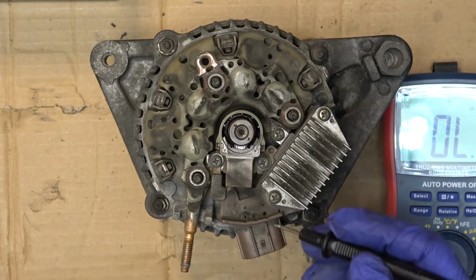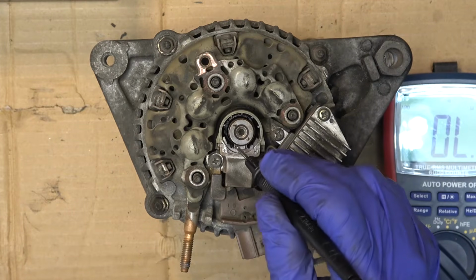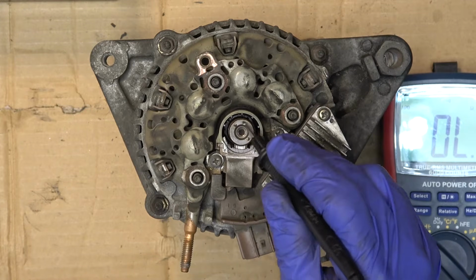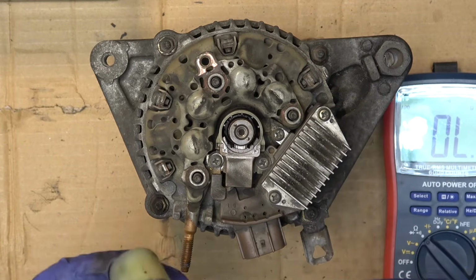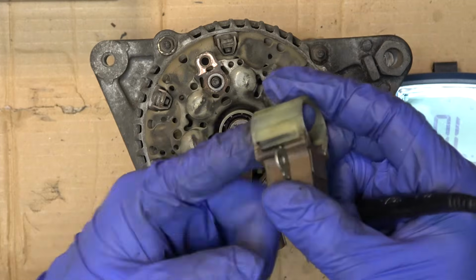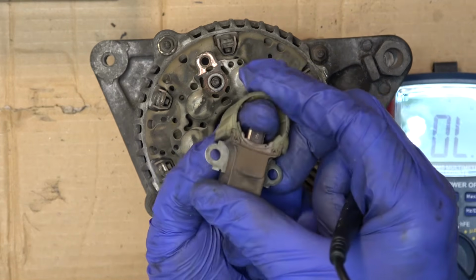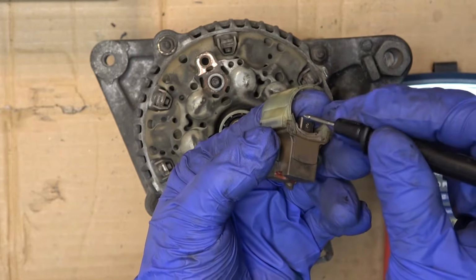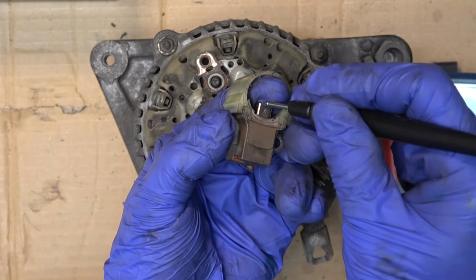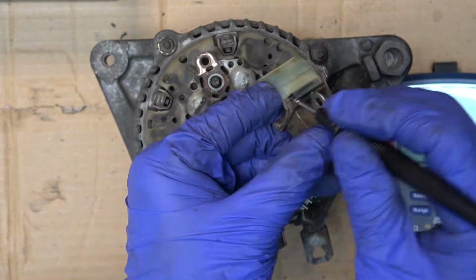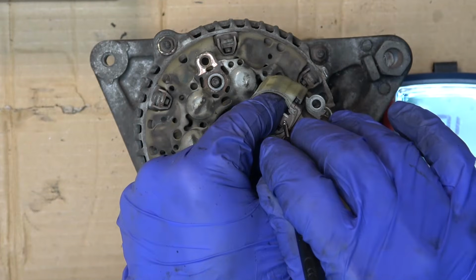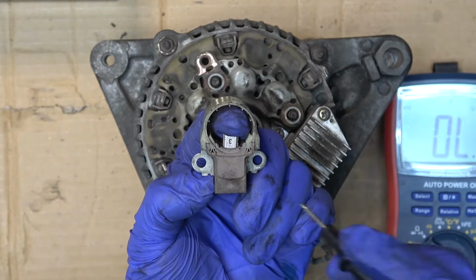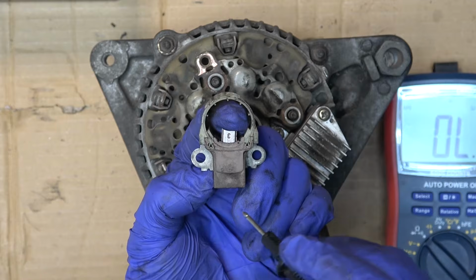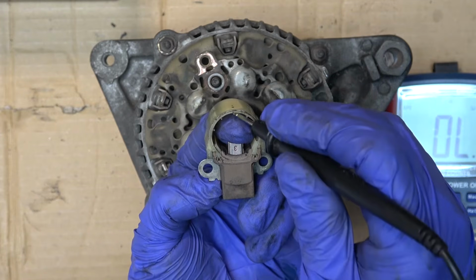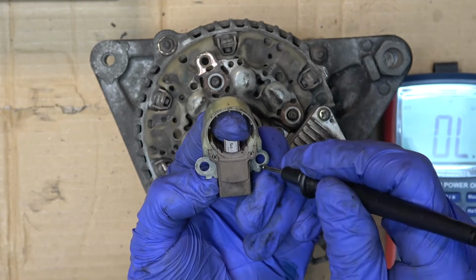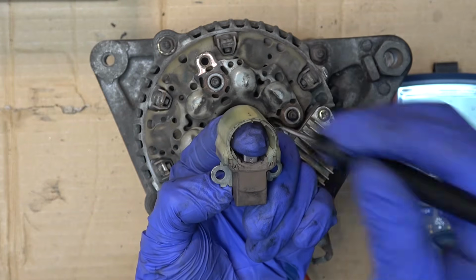Because the two brushes touch the two slip rings on the shaft of the rotor - imagine my finger here is the rotor shaft with two slip rings - one on top that contacts the top brush, and one on the bottom that contacts the bottom brush. You want to measure the continuity between this and the top slip ring, and this and the second slip ring.